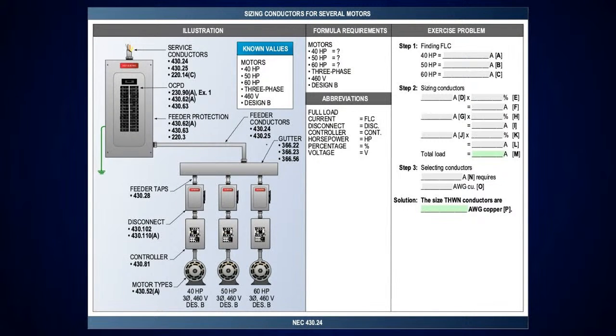So, are single motors always calculated at 125%? Is there any case where you could just take a single motor and calculate it at 100%? Like if it was intermittent duty or something maybe, but I don't know. Well, that's the only thing you would get into. You'd be looking at table 430.22(E) that gives you the values for periodic, intermittent, and those things there. That's the only place I know that you would get away with that. As a matter of fact, we'll show that here in this presentation.